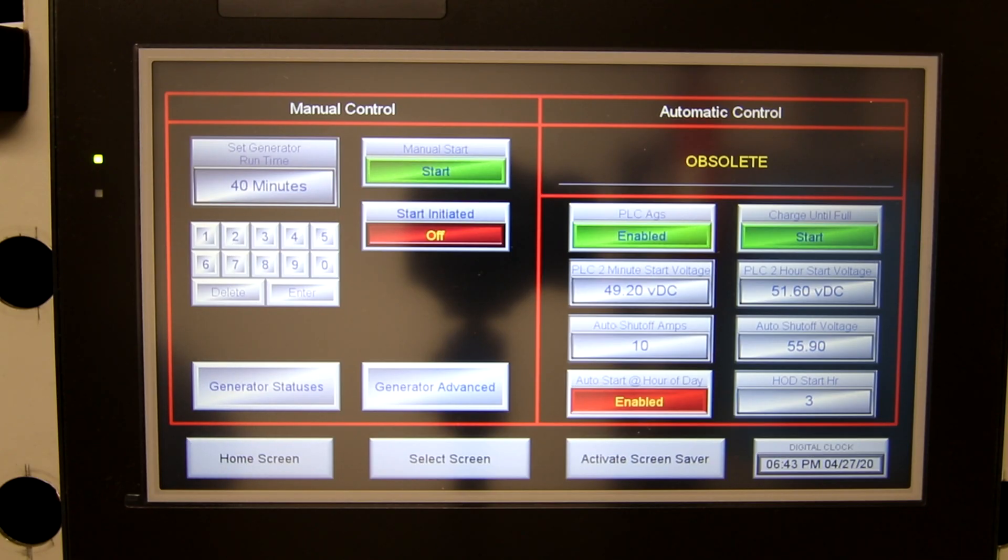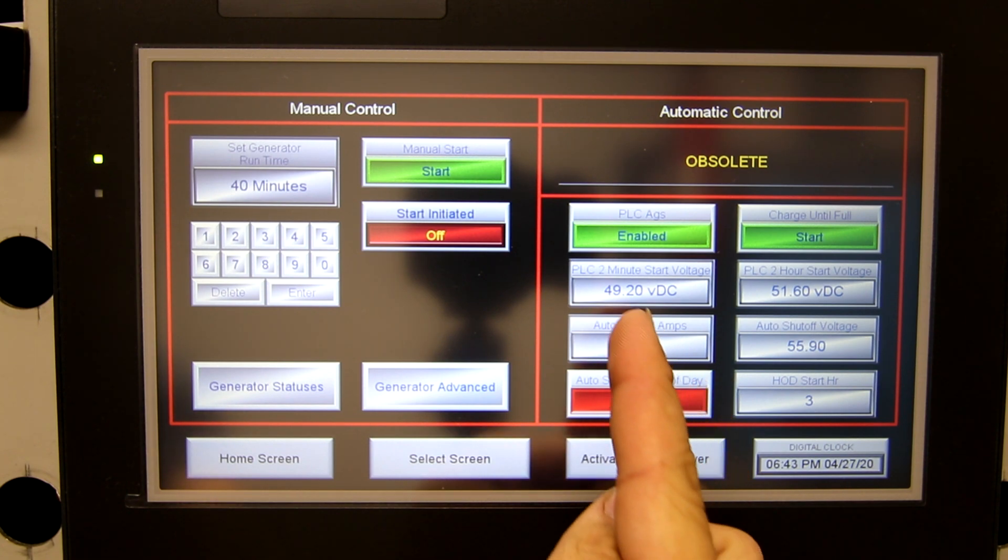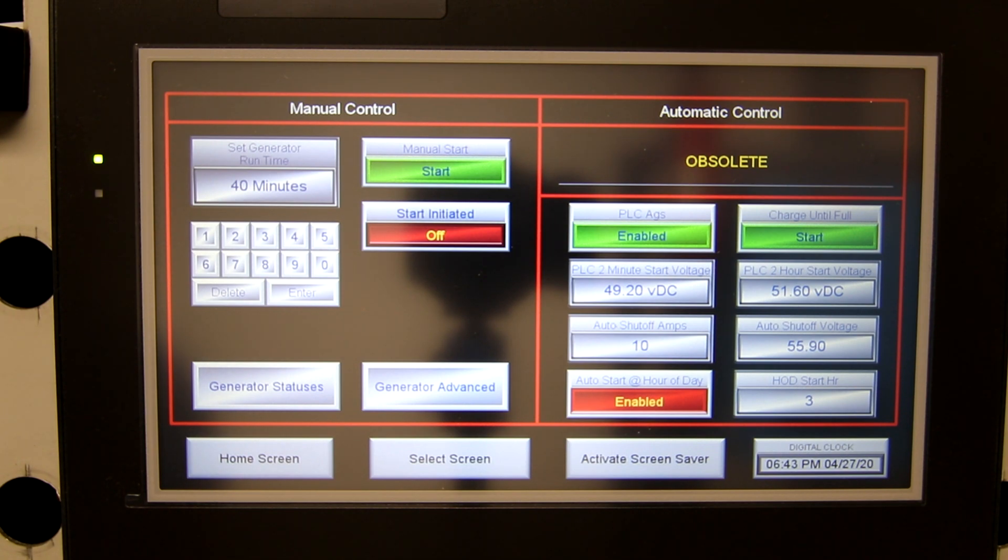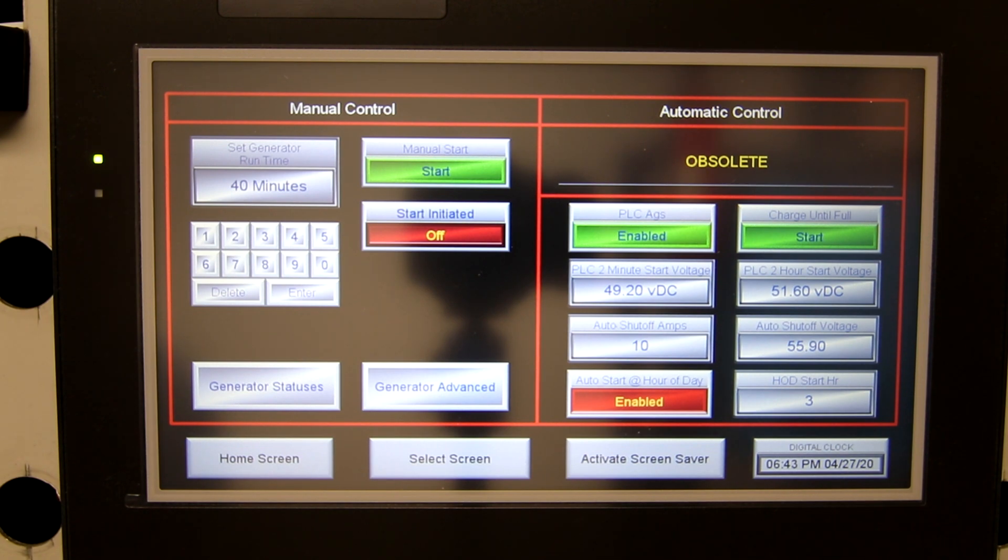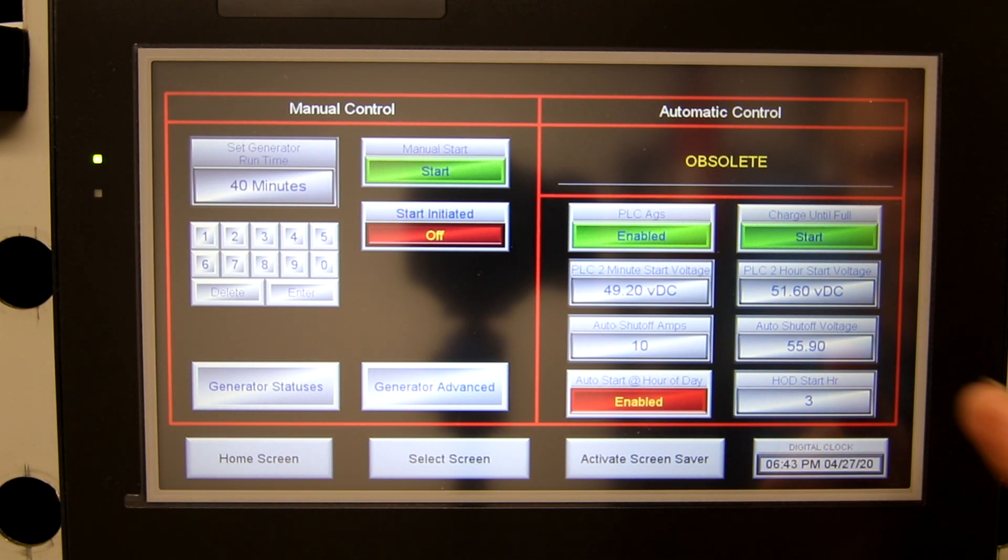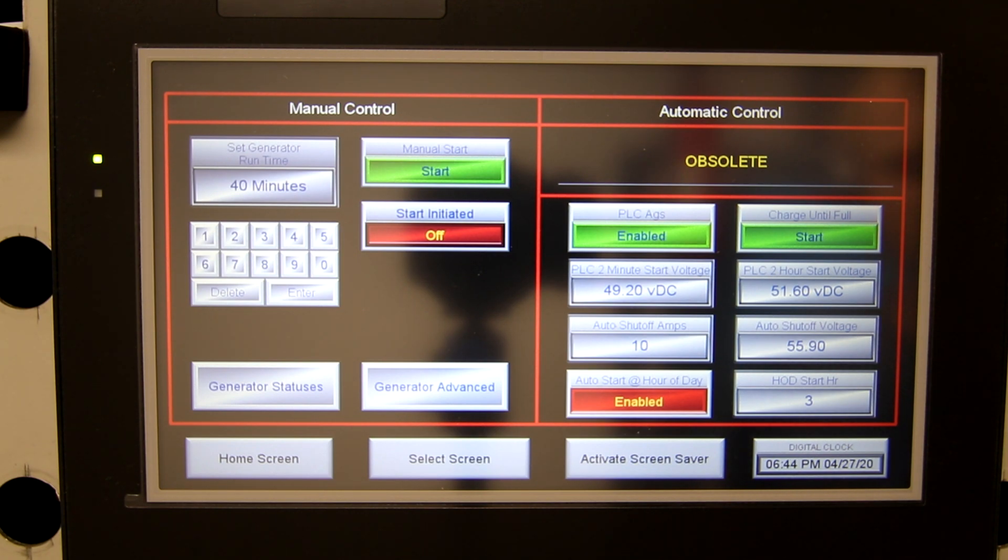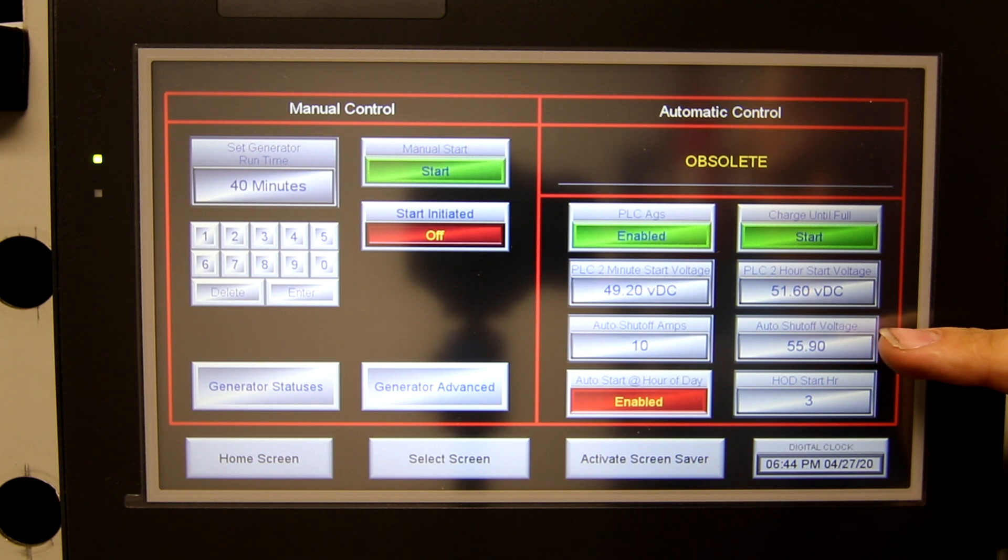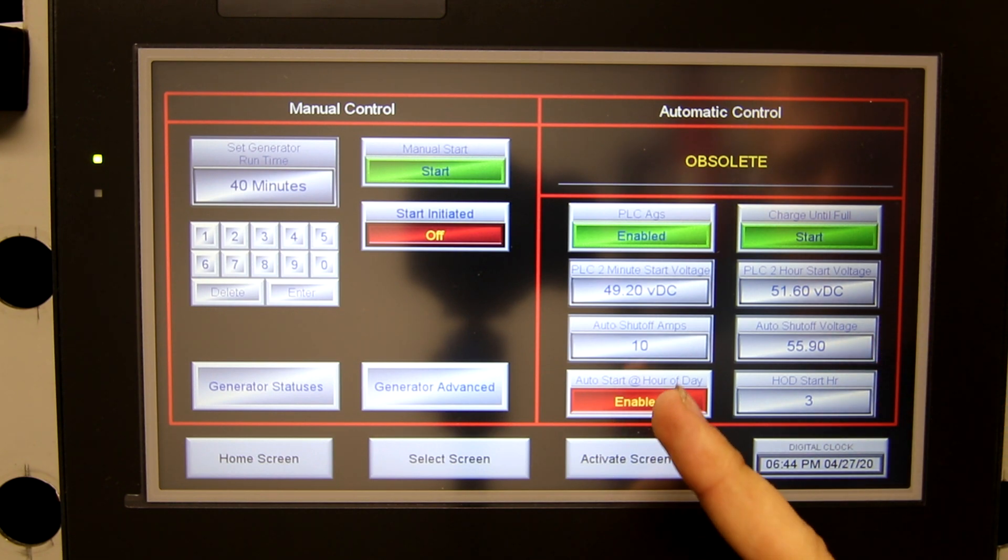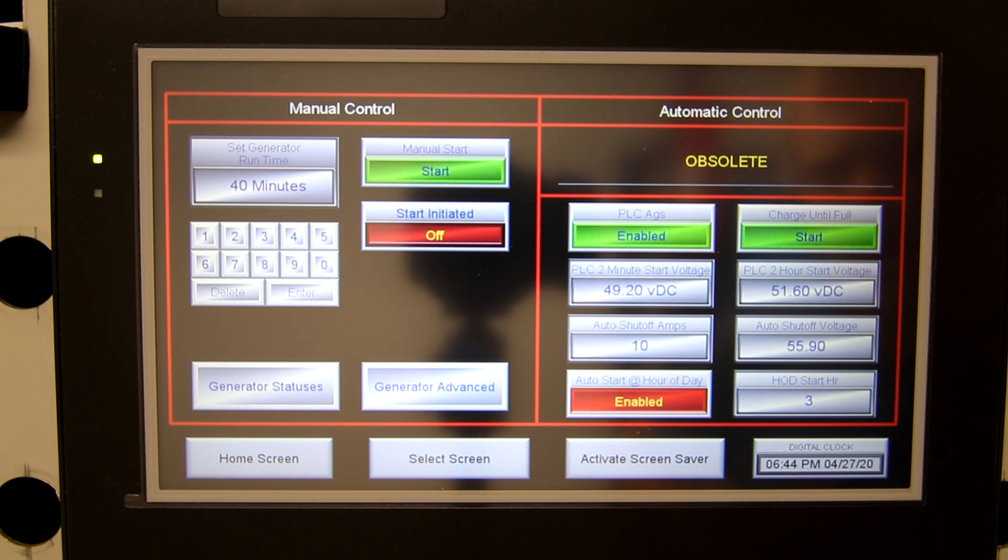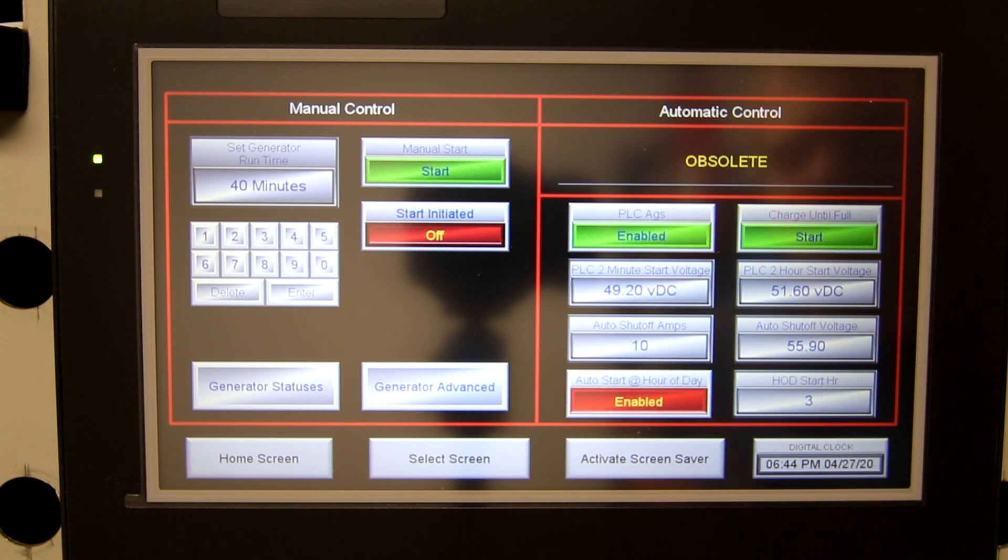So if you take a look, my generator start points I have a 49.2 volt DC two minute start so in other words when it passes 49.2 volts on a discharge it'll start a timer for two minutes and so long as it remains below 49.2 volts for that whole two minutes it'll start up the generator. I have a two hour start voltage of 51.6 volts DC so in other words if it drops below 51.6 volts and stays below 51.6 volts for two hours it'll then trigger a startup cycle and run the generator until the batteries are full and I call the batteries full when they reach a voltage of 55.9 volts and the amperage tapers down to 10 amps. If for some reason there were loads that took the amperage going into the batteries below 10 amps but I wasn't above 55.9 volts it wouldn't shut off the generator so these two conditions must both be met in order for that shutoff to take place.